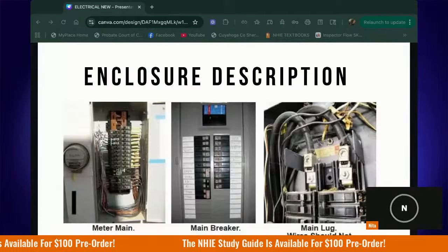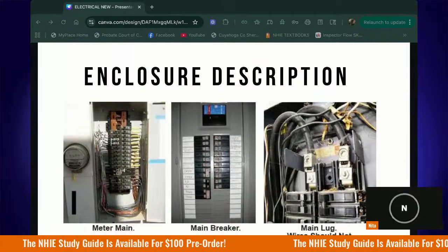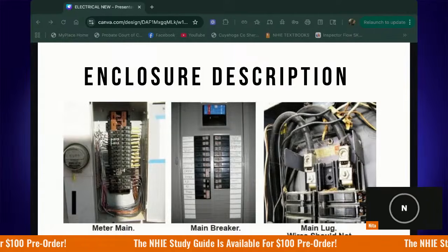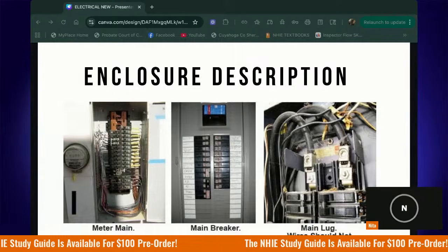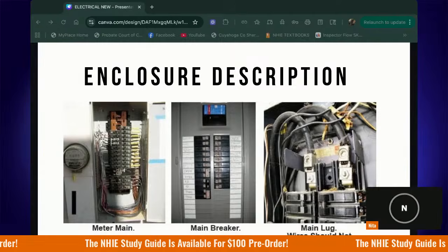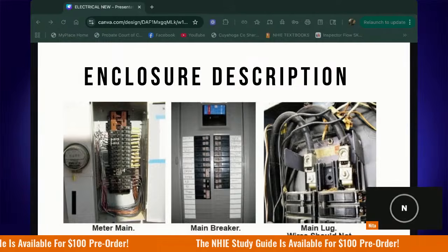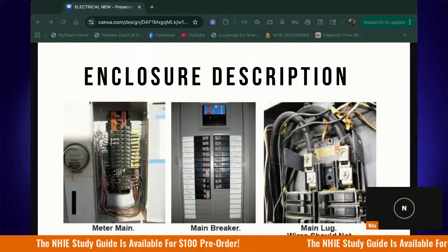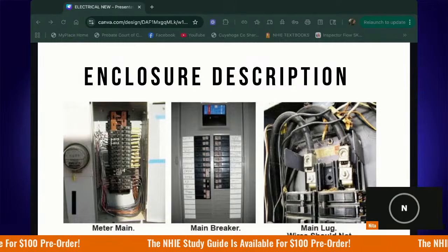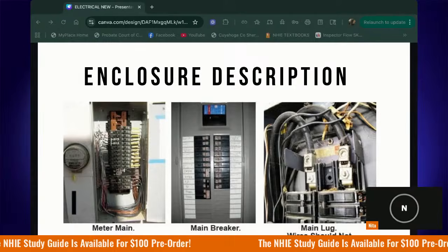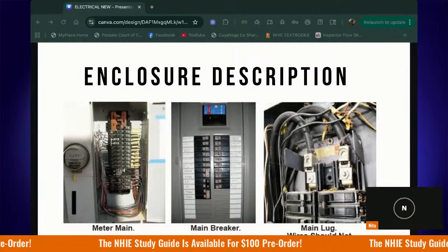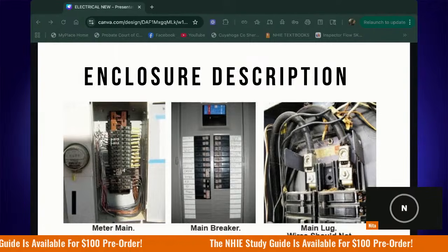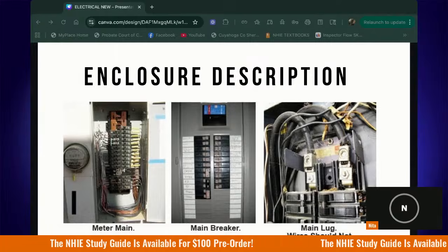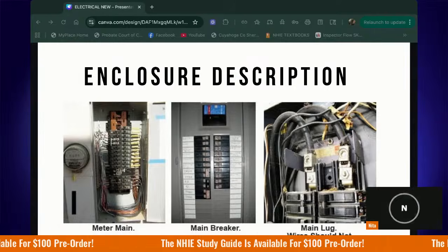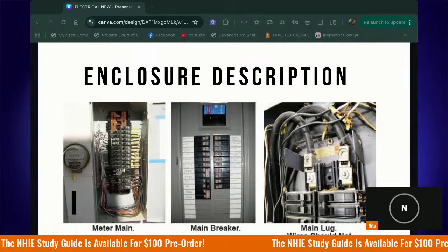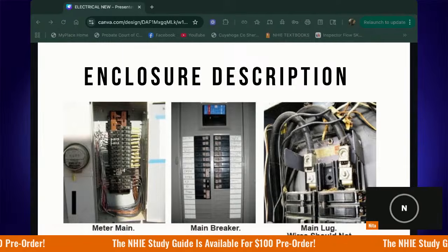And then enclosure. So an enclosure is actually the box. What we call the panel box or the electrical panel or the main panel, it is technically an enclosure. Okay. So it is the box that is holding all of the electrical components. It's usually made of metal, galvanized. So the enclosure is holding or containing all of the energized parts and protecting those electrical components. Again, in slang terms, this is the electrical panel, this is the breaker box. All of that just refers to the enclosure. So the enclosure is the container, and then the panel board is the actual machine inside.